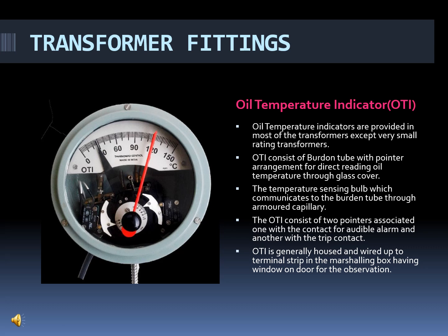The temperature sensing bulb, which is connected to the oil tank, communicates to the Bourdon tube through the armored capillary. See at the bottom side of the OTI, there is an armored capillary. The temperature sensing bulb will communicate the temperature through the Bourdon tube, and the OTI consists of 2 pointers associated with it. One pointer is connected to the audible alarm. Another pointer can be used for a trip contact. The OTI is generally housed and wired up to the terminal strip at the marshalling box, which we have discussed in the previous slides, and has a window on the door for observation.